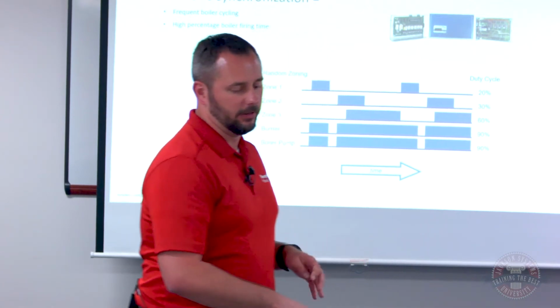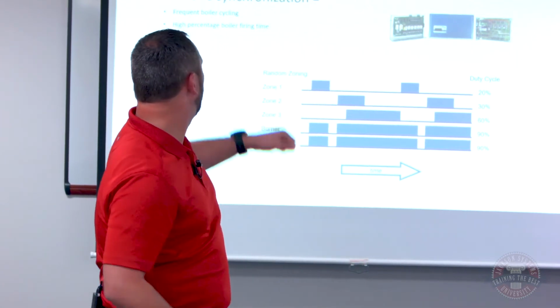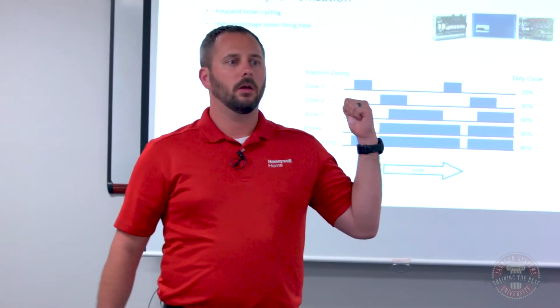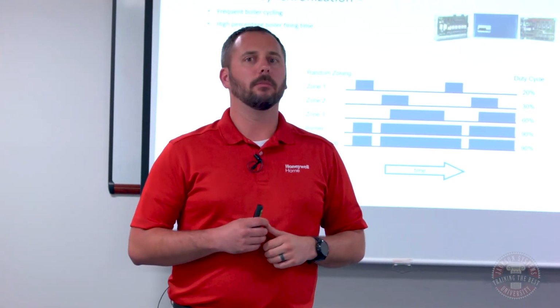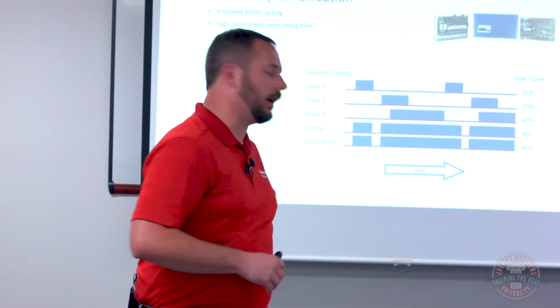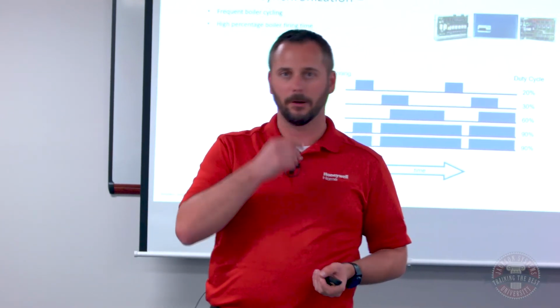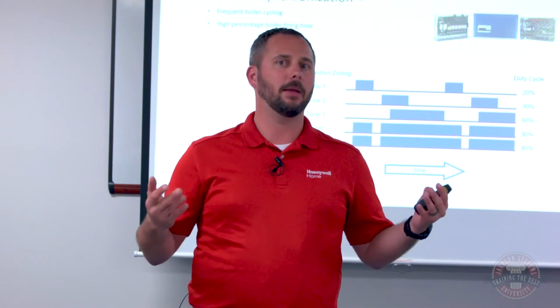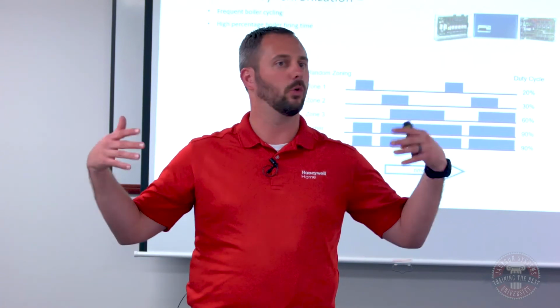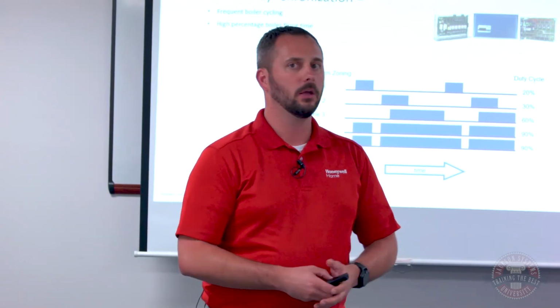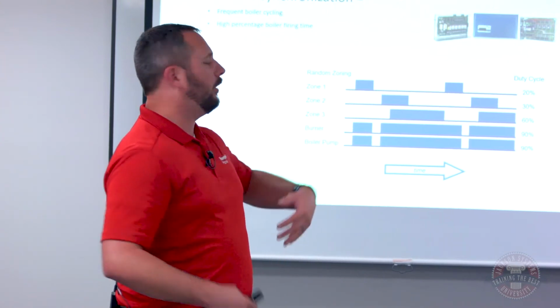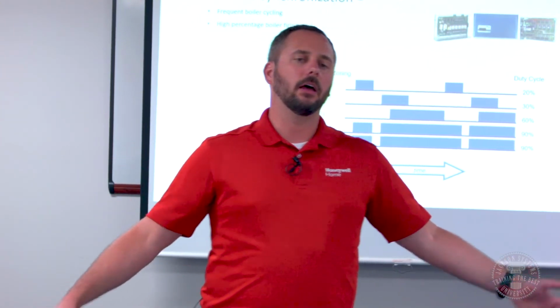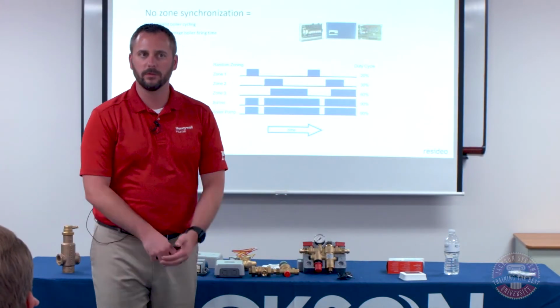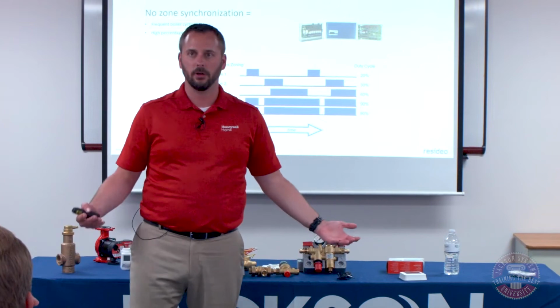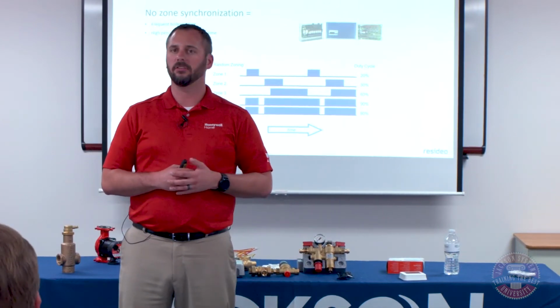So in this example, I've got a 3-zone system, and it's showing what's operating in the system, because with this product, as well as just wiring up with the transformer, we just tell the boiler and the pump to run anytime any thermostat in the house or building or whatever calls for heat. I give an analogy for this. Let's say there's 3 of us going out to a restaurant, we're sitting down and getting some water, and we've got a waiter that's helping us.